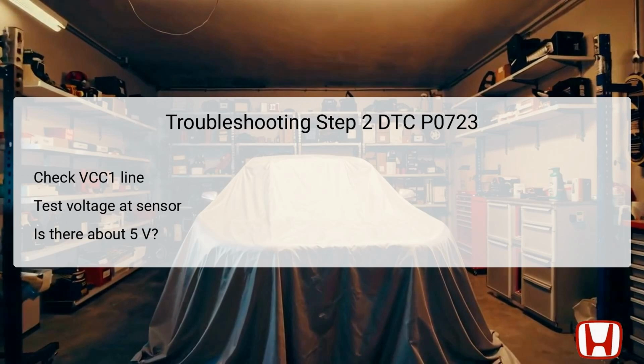Using a multimeter, measure the voltage between test point 1 and test point 2, where test point 1 corresponds to pin number 3 of the sensor connector, and test point 2 is connected to body ground. Ideally, the voltage should be around 5 volts. If this voltage is present, the VCC1 wire is confirmed to be functional, and you will proceed to the next troubleshooting step. If the expected voltage is absent, this indicates an open circuit in the VCC1 line, warranting repair before moving further.